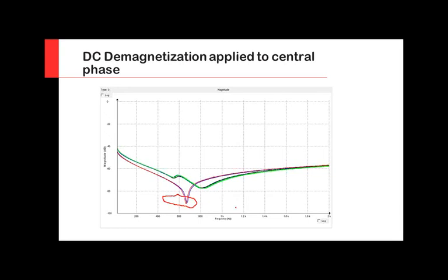I hope you can see what I'm circling right now, because this is a little bit interesting when we're talking about the sweep frequency response and the open circuit. Everybody expects it to be just one on top of the other. There might be something else that we need to take into account. Same thing here. When we look at the response of the symmetrical phases, it's almost overlapping one on top of the other, but there's a little tiny deviation.